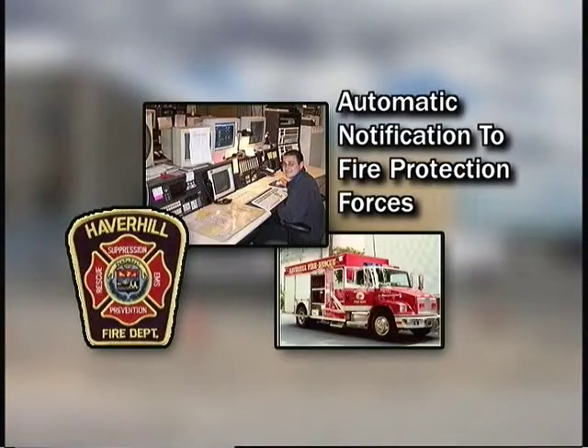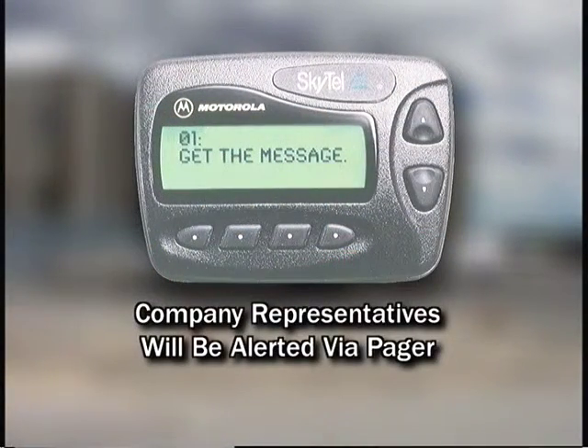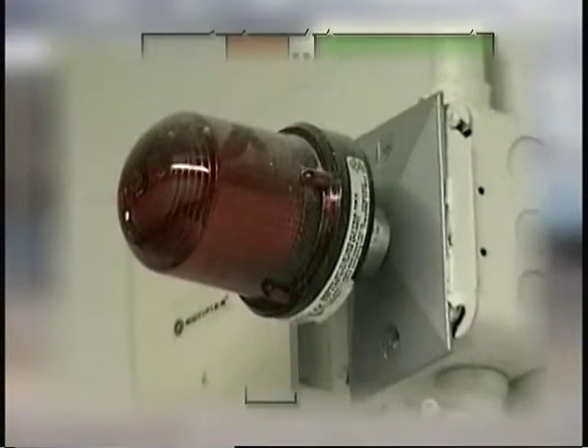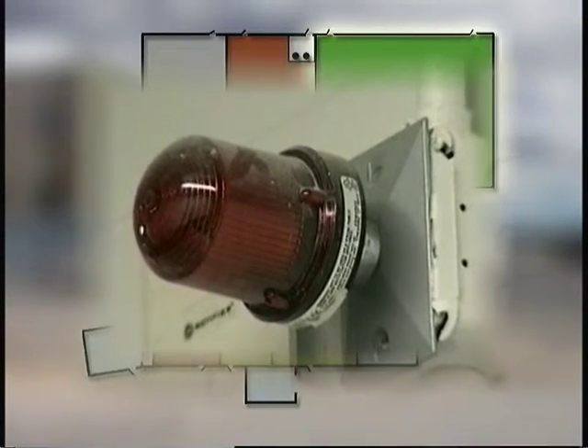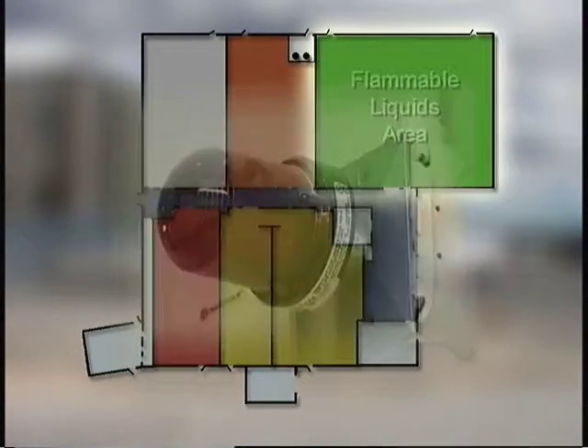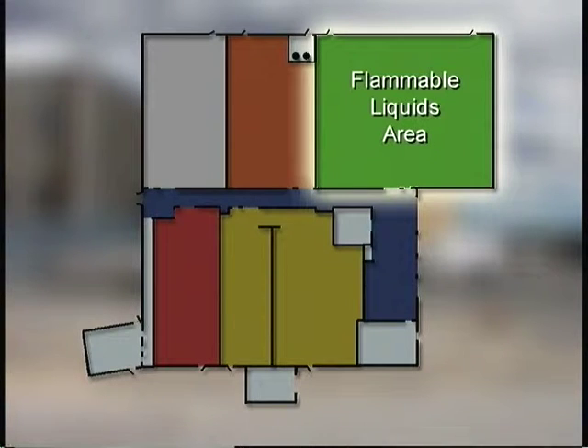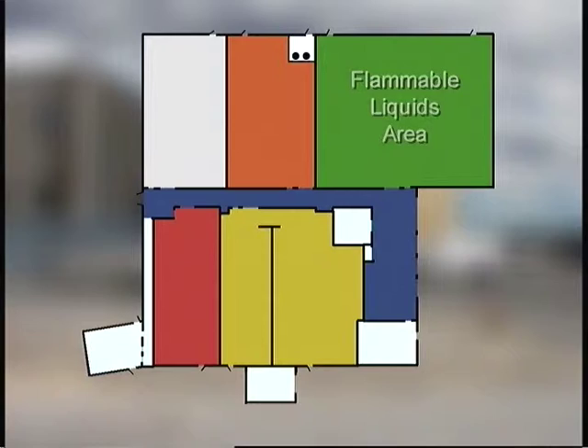Upon alarm, the system will provide notification to local fire protection forces via the master box. A representative of Alfa Aesar, the general manager and/or the chemical inventory manager, will be contacted via beeper. A rotating beacon will operate outside the affected space. The flammable liquids area is the only area using the AFFF system. All other spaces in the building use the wet pipe sprinkler system.